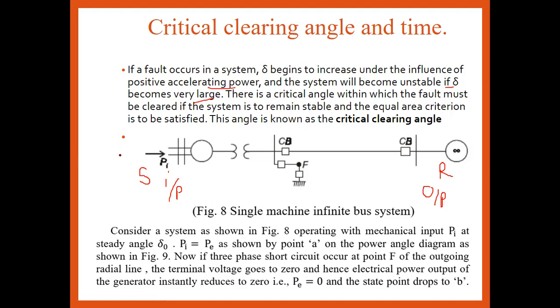This angle is called the critical clearing angle — that is the value of delta before which the fault on the system must be cleared, so that the system remains under stable condition and the equal area criteria is satisfied. Equal area criteria means A1 equals A2 — that is accelerating power equals de-accelerating power — or Pi equals Pe must be satisfied before the system reaches an uncontrollable or unstable condition. This angle is called the critical clearing angle.